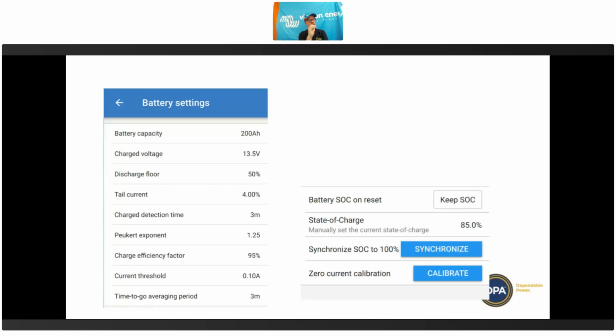But by itself, the battery monitor doesn't do that. And again, with the MPPT, usually the MPPT can't do that either, except the small ones that have a load terminal, and I'll show you that in the next section. But mostly if you have DC loads, then you need to have a battery protect to switch that off when the voltage gets too low. And it's separate to this.